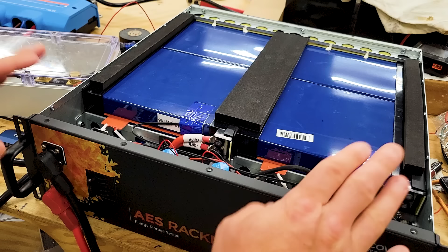Now I took the cover off the battery because the next test is going to be testing the heating system. This battery has these silicone heating pads. They're kind of orange, and they run underneath all the cells. So every cell is in contact with a heating pad. If the battery gets too cold, it will turn on the heat. Now it can do that under a few different situations that are spelled out in the manual, but that includes under charging conditions. So I'll pull out one of these temperature sensors.